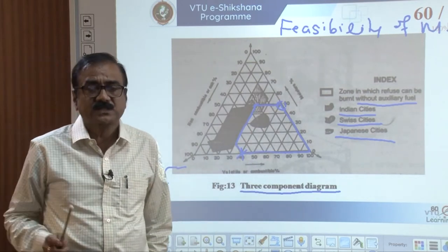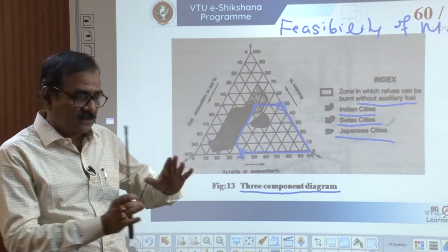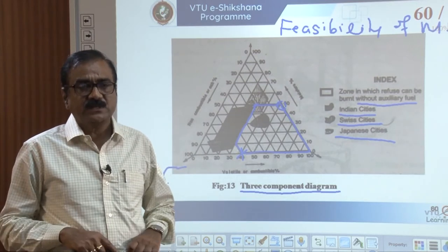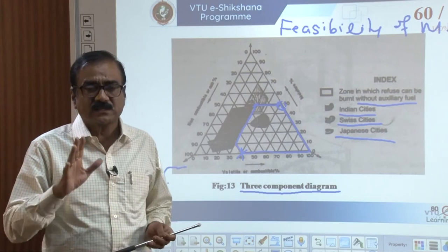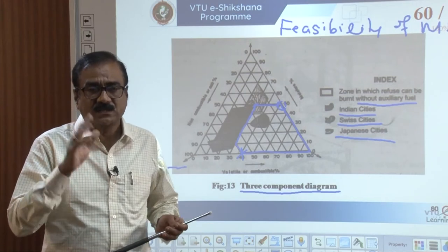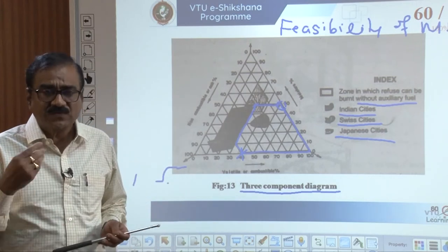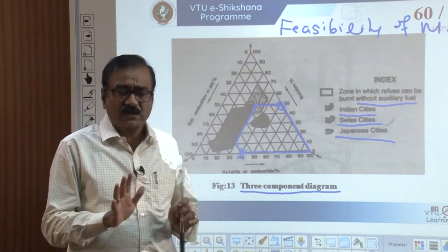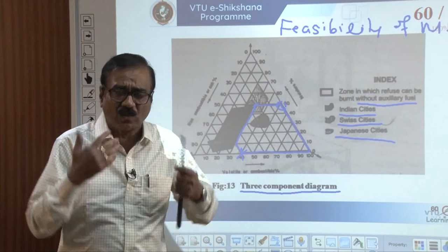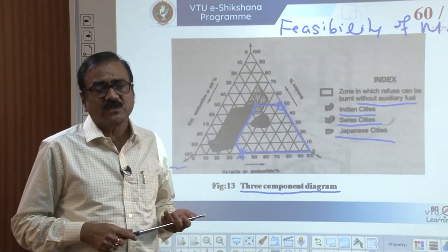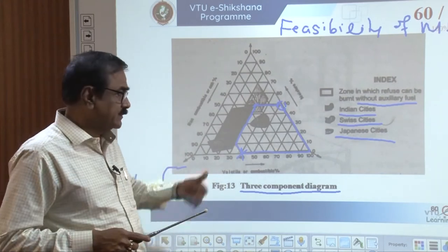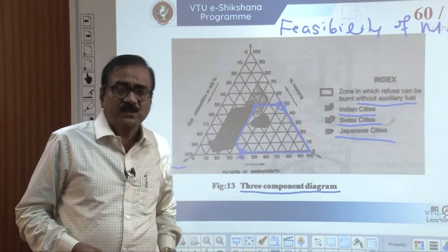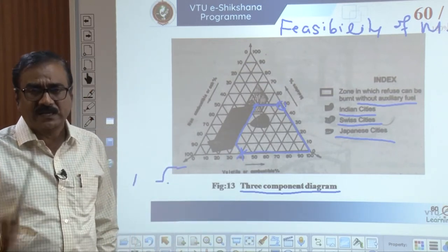You have to study all the properties and draw a three-component diagram for the particular municipal solid waste, then decide whether it is feasible or not. If not feasible, a little additional auxiliary fuel can be added, and the quantity of auxiliary fuel required can also be calculated. This is a very important diagram known as the three-component diagram in municipal solid waste incineration.